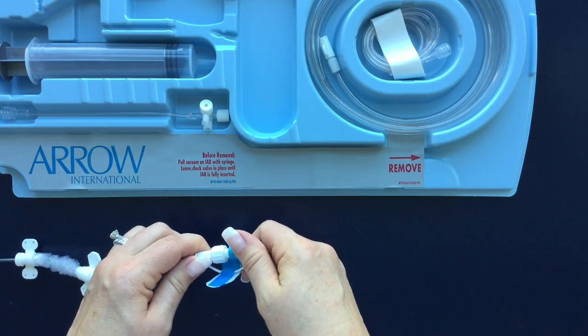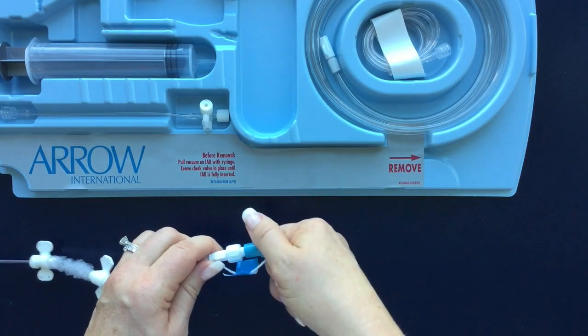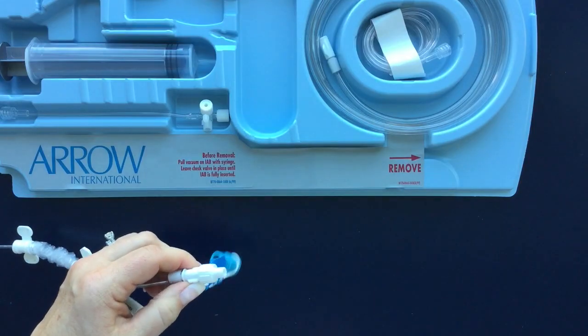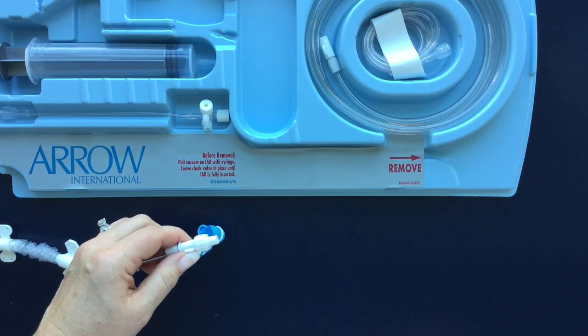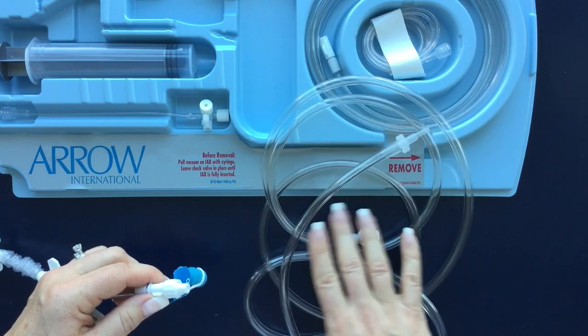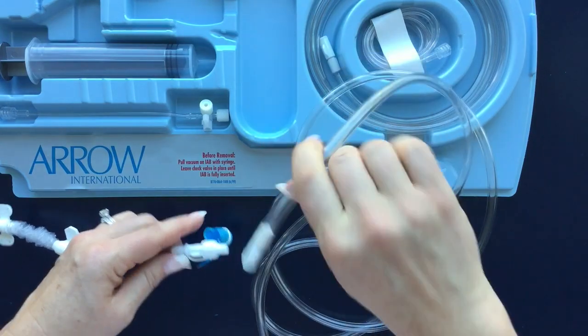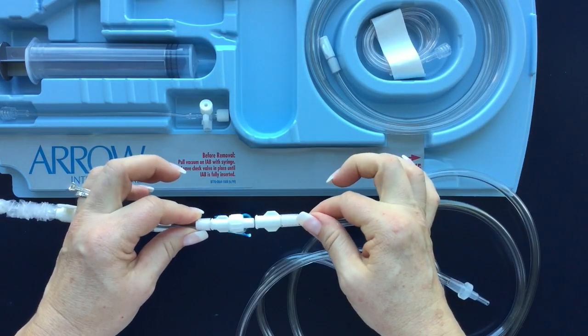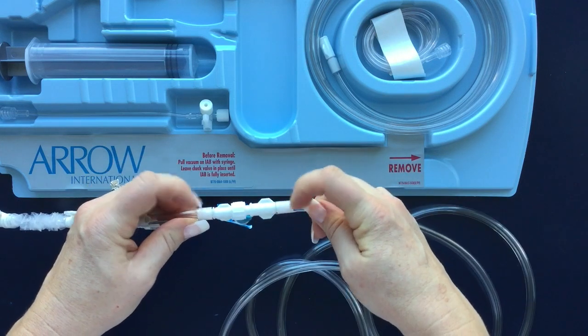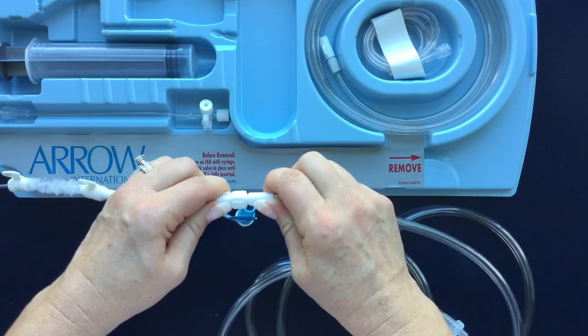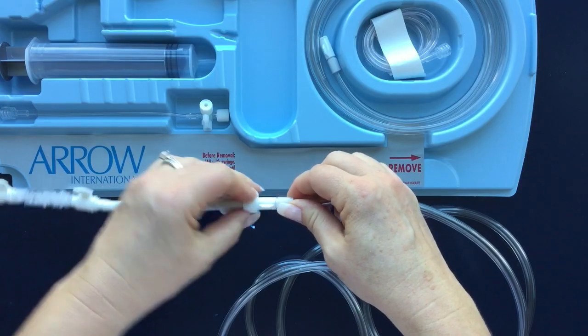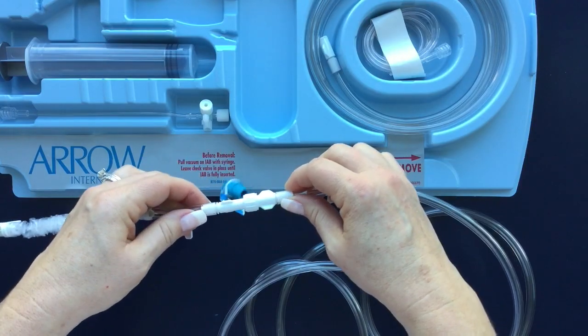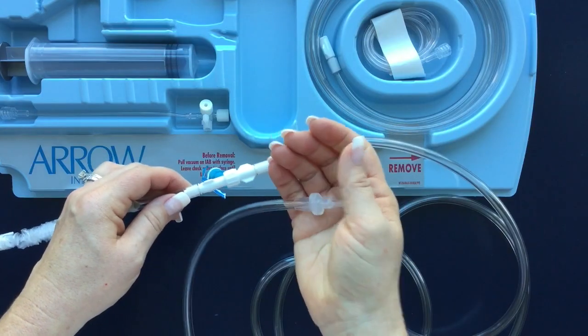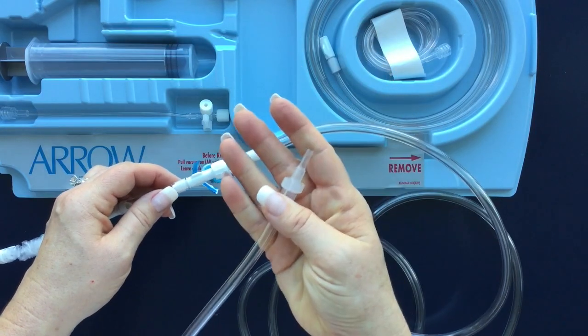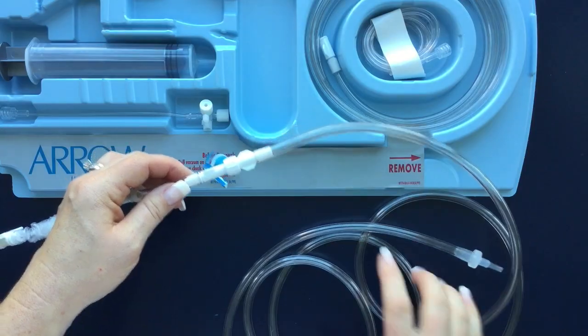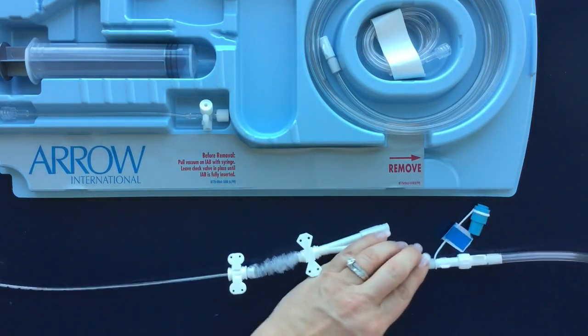Last thing is going to be to connect our helium drive line. I'm going to now disconnect that one-way valve because we are inside the patient, and then I'm going to utilize that separate package of tubing to connect to a Maquet console. I'm going to connect the 2 white ends using the wingtips, push and twist to seal that connection. Then I use the locking nut to simply secure it down. You'll then hand this off to your circulator where it can be connected into your helium supply on your Maquet console, and you may begin pumping.